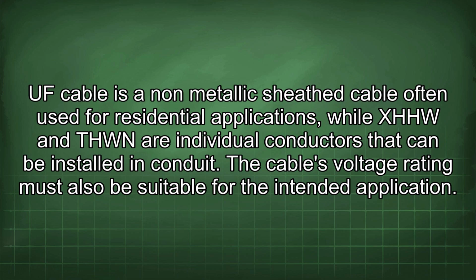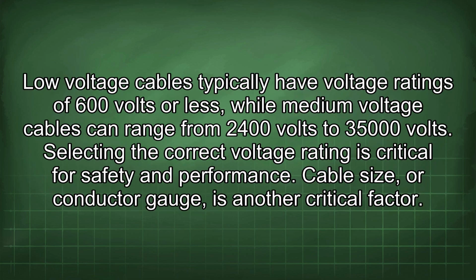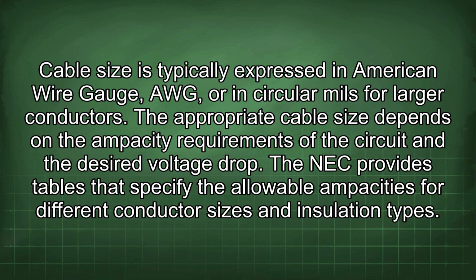The cable's voltage rating must also be suitable for the intended application. Low voltage cables typically have voltage ratings of 600 volts or less, while medium voltage cables can range from 2400 volts to 35,000 volts. Selecting the correct voltage rating is critical for safety and performance. Cable size, or conductor gauge, is another critical factor. Cable size is typically expressed in American wire gauge (AWG), or in circular mils for larger conductors. The appropriate cable size depends on the ampacity requirements of the circuit and the desired voltage drop. The NEC provides tables that specify the allowable ampacities for different conductor sizes and insulation types.